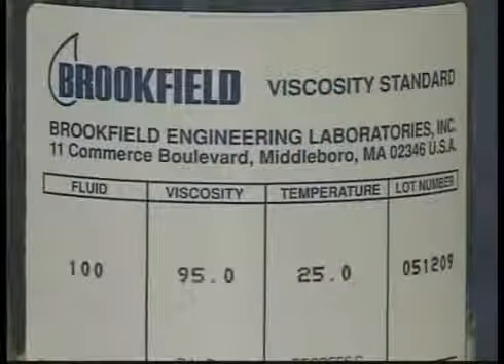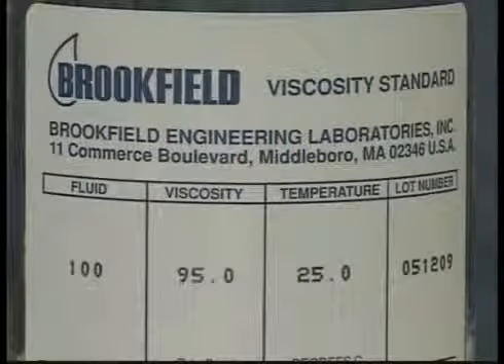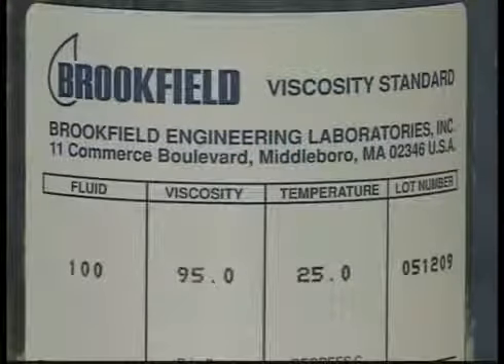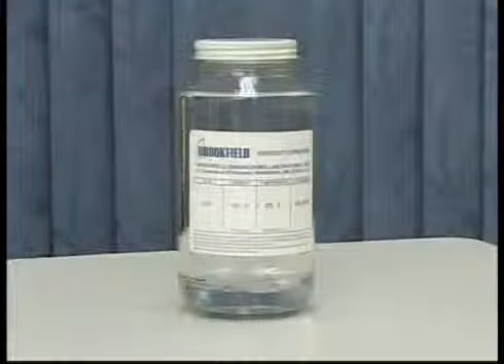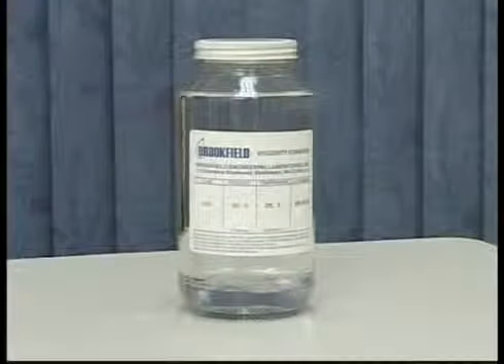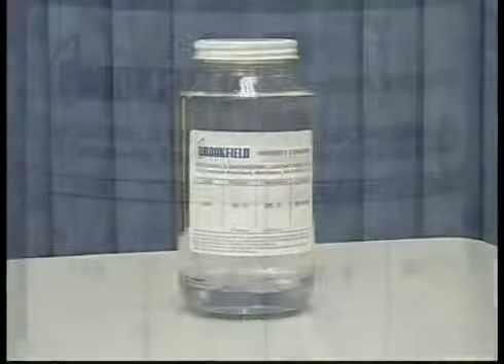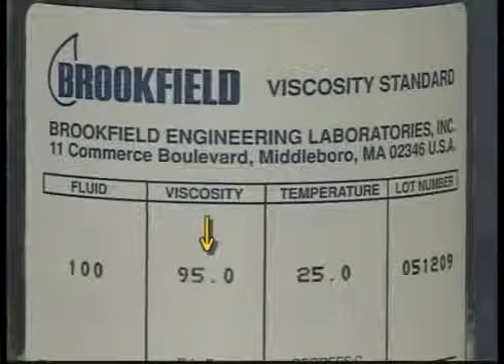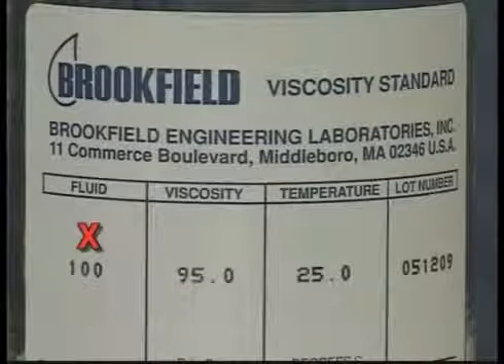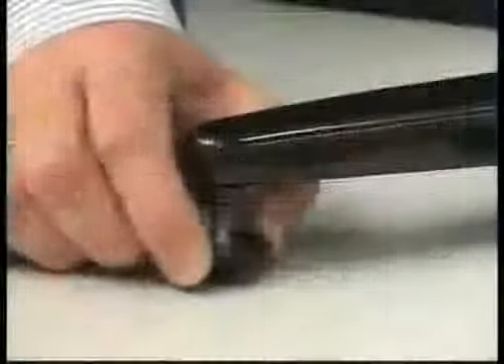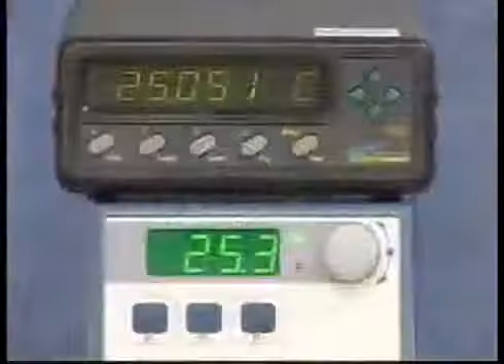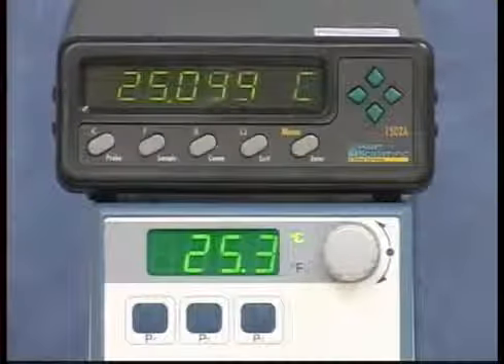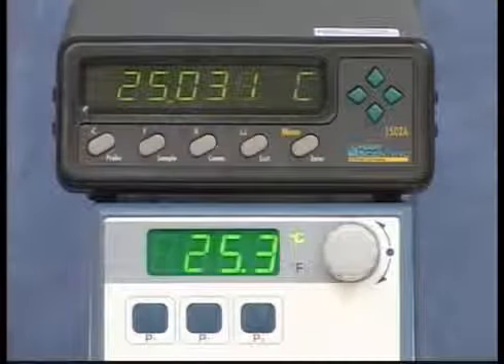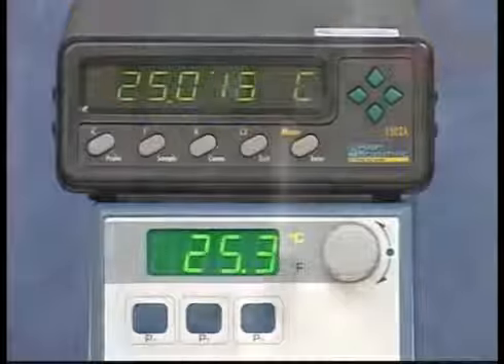This being the case, a 100 or 500 centipoise silicone fluid can be used. These lower viscosity fluids are easier to work with and to clean. Use the actual value of the fluid, not the stated value, for the calibration check. Make sure the instrument is level. The viscosity standard fluid needs to be equilibrated at 25 degrees Celsius to get an accurate reading.